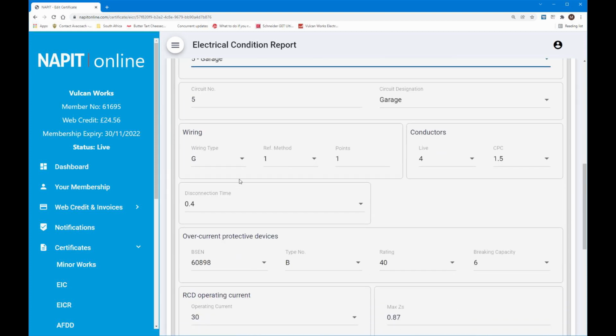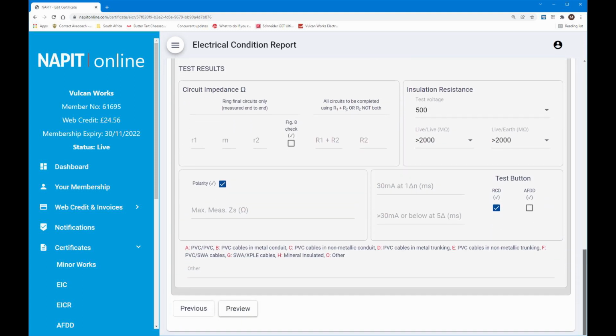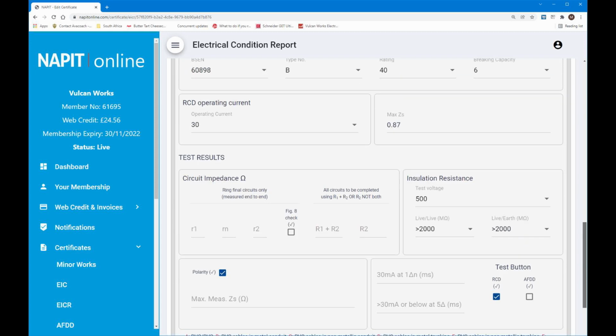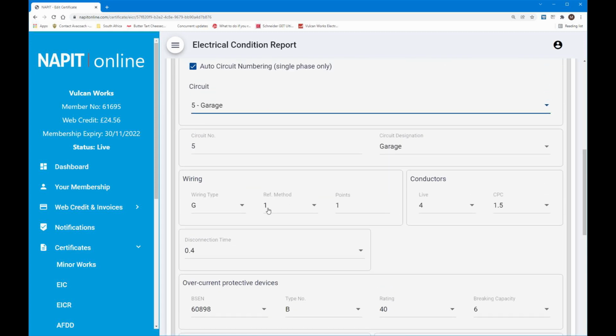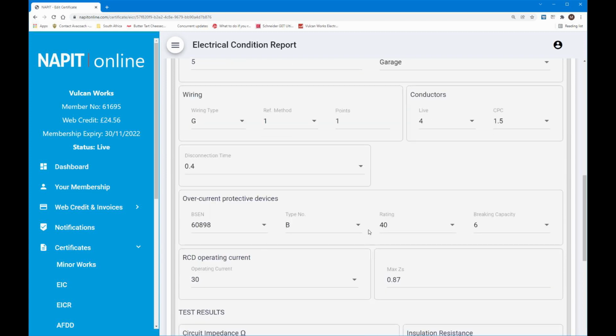Now this is the only one where the wiring type was different. And if you go all the way down to the bottom, type G is an XLPE cable. Okay, reference method is 1. It's just in fresh air. And only 1 point because it's the garage consumer unit. It was done in 4mm with a 1.5 CPC. 60898 type B. Now, yes, I got that wrong in the EIC, which I've now corrected. It's a 40 amp circuit breaker, not a 32 that I stated. I made that mistake, so it's a 40.